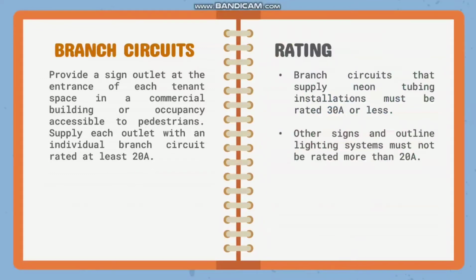For the rating naman, branch circuits that supply neon tubing installations must be rated 30 ampere or less. Other signs and outline lighting systems must not be rated more than 20 amperes. So, for neon tubing, 30 amperes or less, and for the other signs is 20 amperes. So, take note of that.